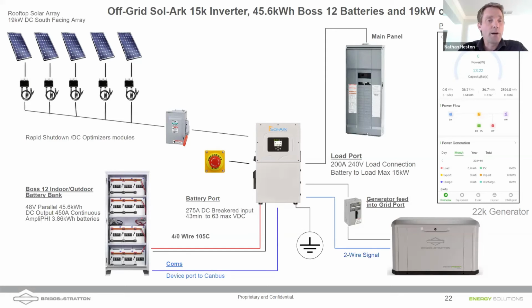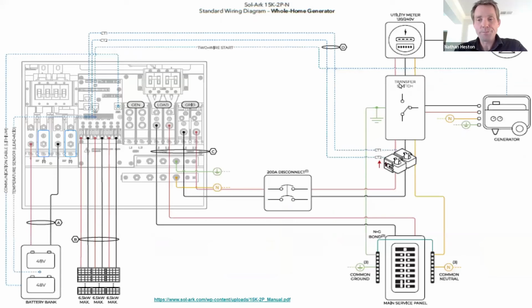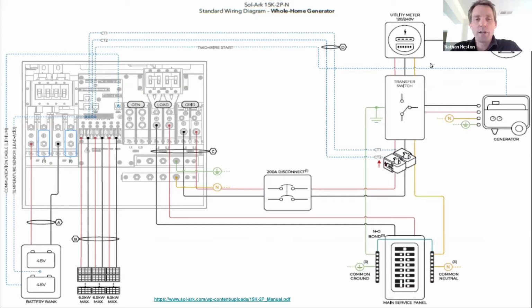We're looking at an outdoor rated Boss 12 cabinet down there for the batteries. And then backing up the main loads panel. Of course, there's only going to be a single loads panel for an off-grid application. Similarly, showing DC coupled. Now, John, my colleague Daniel wanted to get into this one a little bit, and I did as well. I mean, you mentioned it earlier. We're showing a similar example here.